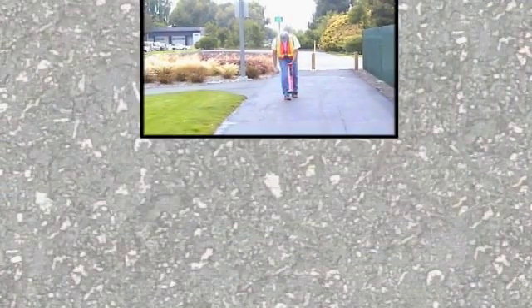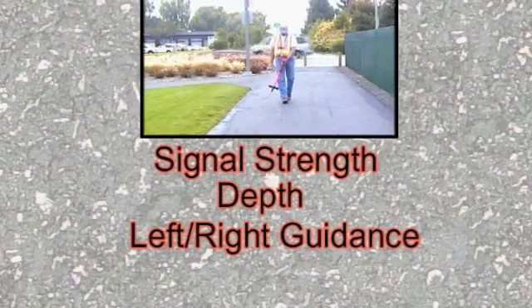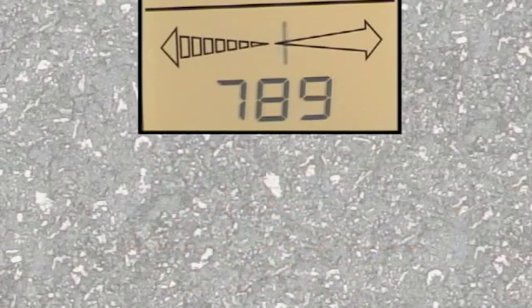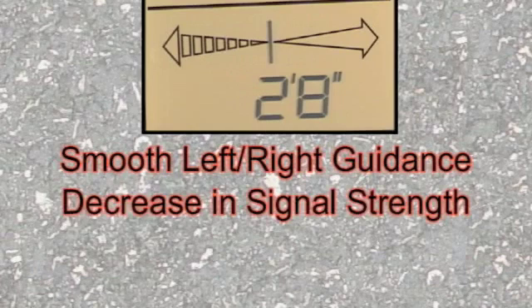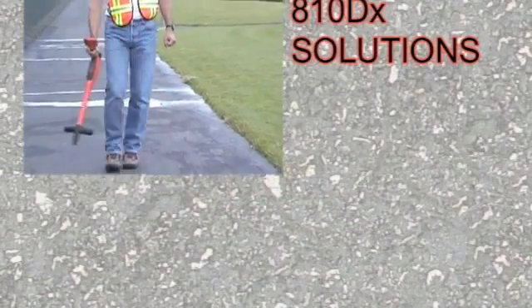As you continue your locate, you can use signal strength, depth, left-right guidance, and the audible tone to keep you on target. A good locate is generally characterized by smooth left-right guidance, a gradual decrease in signal strength, and consistent depths. Because of underground congestion and common construction practices, you will routinely encounter situations that will disrupt your locate, including changes in conductor direction, T's and laterals, and changes in depth. The Metrotech 810DX is designed to help you get back online quickly and easily.